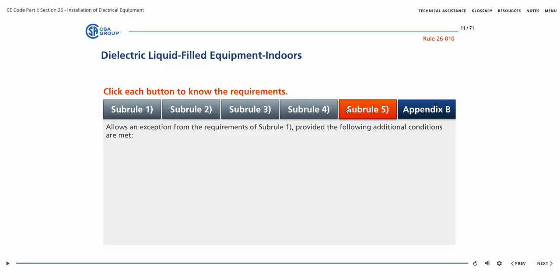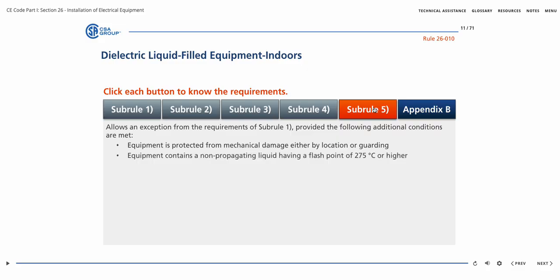Sub-Rule 5 allows an exception from the requirements of Sub-Rule 1 for dielectric liquid-filled equipment located indoors with more than 23 liters of liquid in one tank or more than 69 liters in a group of tanks, provided the following additional conditions are met. Equipment is protected from mechanical damage either by location or guarding. Equipment contains a non-propagating liquid having a flash point of 275 degrees Celsius or higher.